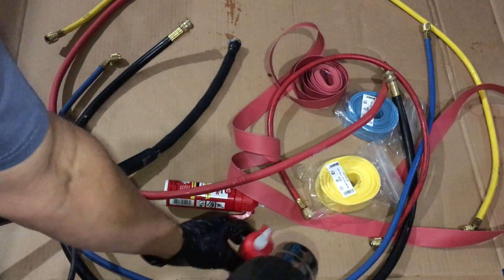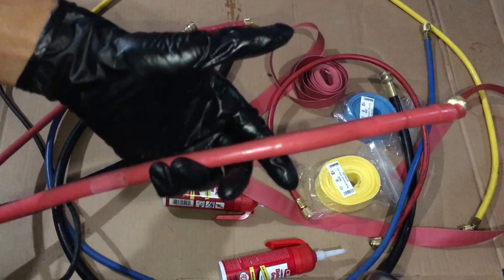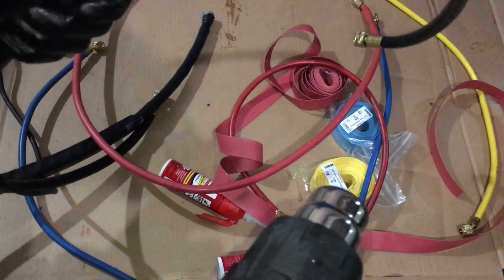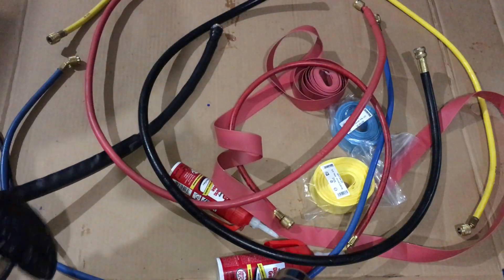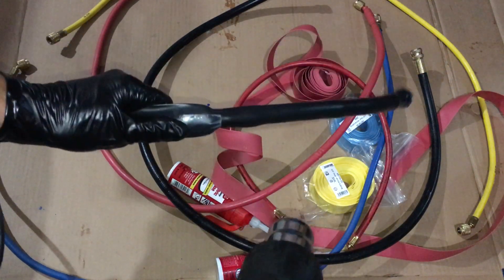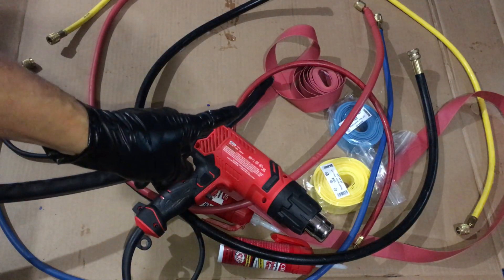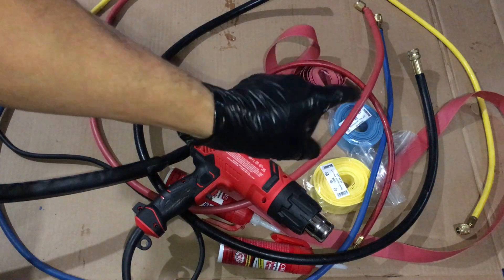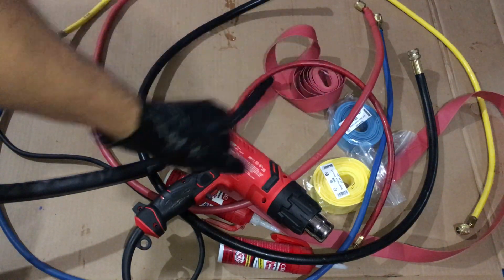That is my tech tip for today. For those of you who buy good hoses — if you buy a 60-inch pair of Yellow Jacket hoses you're paying like 69 to 70 dollars for a set, and the big three-eighths Yellow Jacket charging hose by itself is approaching a hundred dollars. So you don't want it to break. That was the video for today for extending the life of refrigerant hoses and hopefully making them so when you pull a vacuum, you don't lose the vacuum through the hoses. See you guys later.